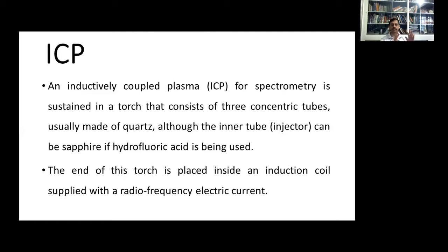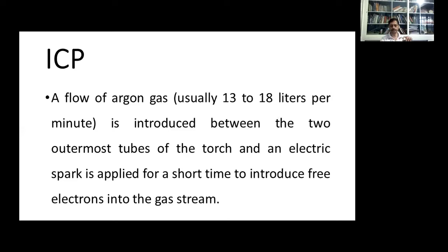A flow of argon gas, you know that argon is a neutral gas which is selected for ICP. A flow of argon gas at a rate of about 13 to 18 liters per minute is introduced between the 2 outermost tubes, that is 2 quartz tubes of the torch, and an electric spark is applied for a short time to introduce free electrons into the gas stream.